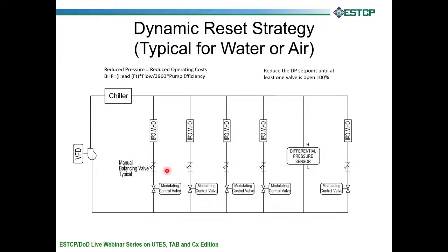So the purpose of this slide is your balancing contractor not only has to balance these valves, again, he has to tell the control contractor what differential set point to use. So he balances everything at 100% flow. He looks at the differential pressure transmitter. He sees that he has 10 psi. He tells Mr. Control Contractor, I need a 10 psi set point, and the control contractor programs it in, and that controls the pump, and everybody's happy.